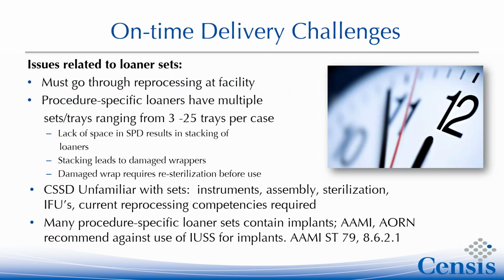Loaner sets or vendor trays have their own set of challenges. First, they must go through reprocessing at the facility. Even if they arrive neatly wrapped and looking ready for the OR, the facility has no way of knowing under what conditions the assets were transported or whether proper sterilization processes were followed. Ultimately, the facility is responsible for ensuring the sterile integrity of the tray or set, so it must go through their own reprocessing loop. It's really important for vendors to deliver sets well in advance of a case, so sterile processing has sufficient lead time to follow their procedures.